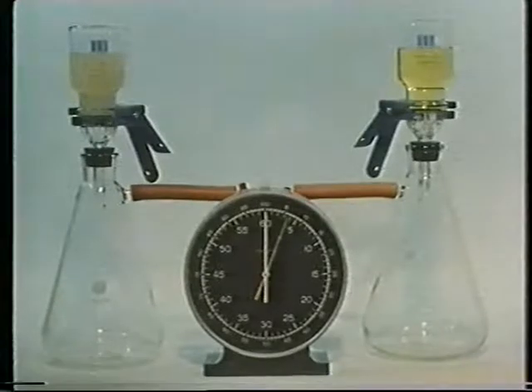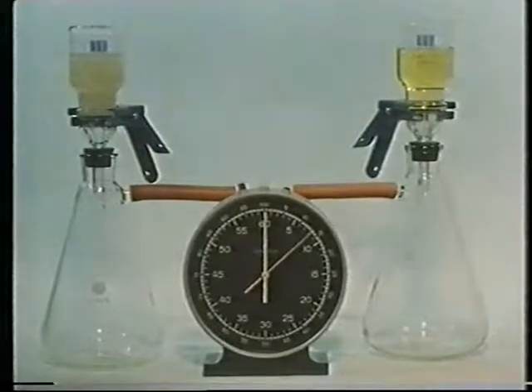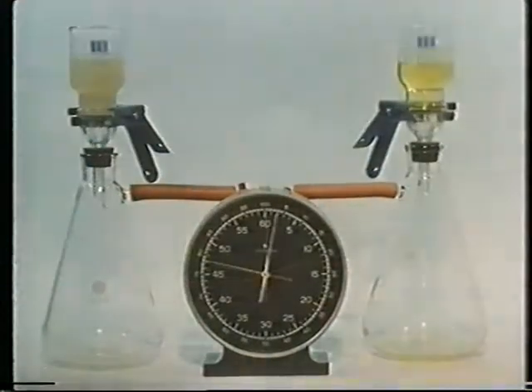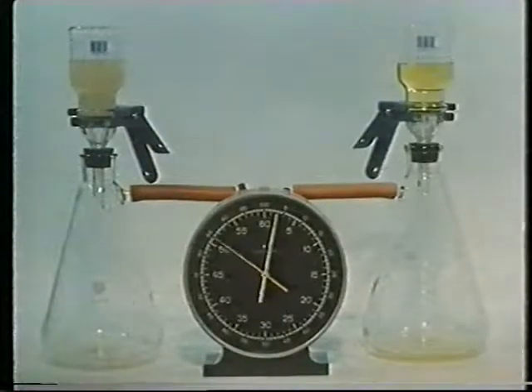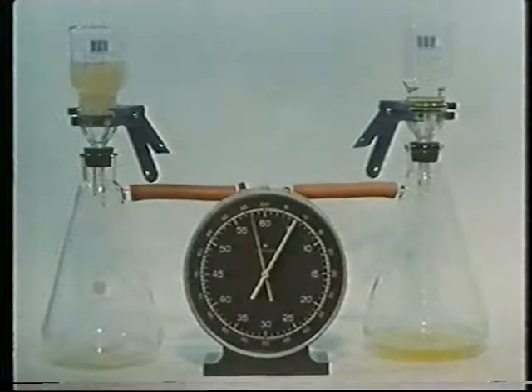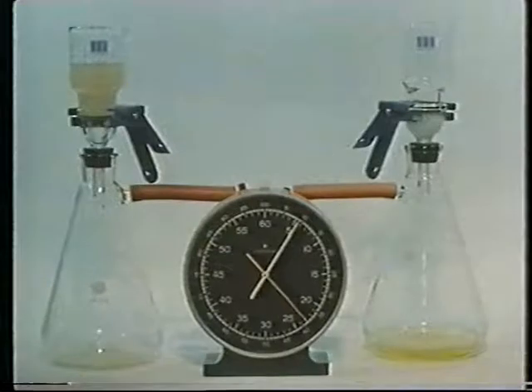Water in oil can also cause blocked filters. The oil sample on the left is contaminated with water. The one on the right is not. The sample on the right flows faster, because it passes freely through the filter. The flow on the left is slower. The filter has become blocked, due to the interaction of the water with some of the oil's components.